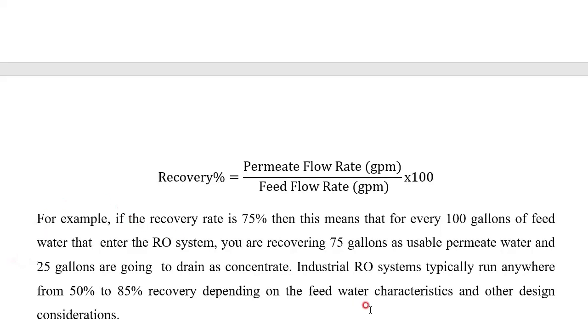Usually industrial RO systems run between 50 to 85% recovery rate. That is, they recover about 50 to 85% of the water that has been fed into their system.